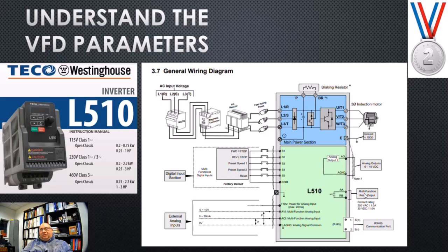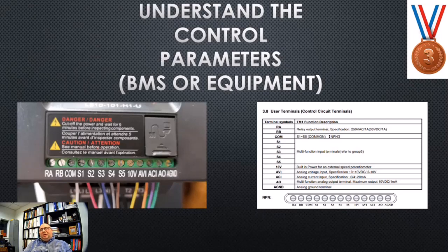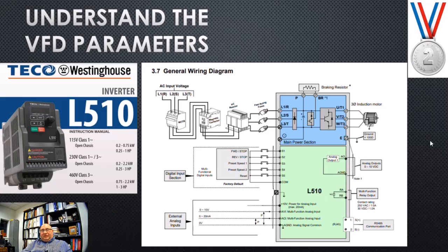We also have a multifunction output relay, which is really neat because we could use this as an alarm relay output, so we know if there's a failure on the drive. And we have an RS-485 communication port. Some drives could do Modbus, they could do BACnet, they could do LON. So you could actually have a BMS network that you could talk to and network the drives independently. But we also want to understand the terminal layout. On this terminal layout, we could also look at this particular diagram here. These are our inputs that are binary, discrete. These are inputs that are analog.